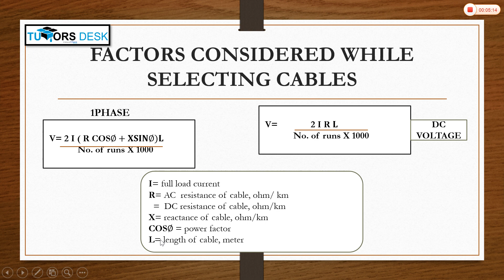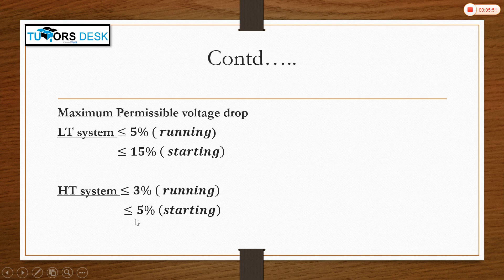You should also know the maximum permissible voltage drop. For LT system, for the running condition, it should be less than or equal to 5%, and for starting condition, it should be less than or equal to 15%. Starting condition occurs generally in the case of motors. For HT system, it is less than or equal to 3% for running and less than or equal to 5% for starting.